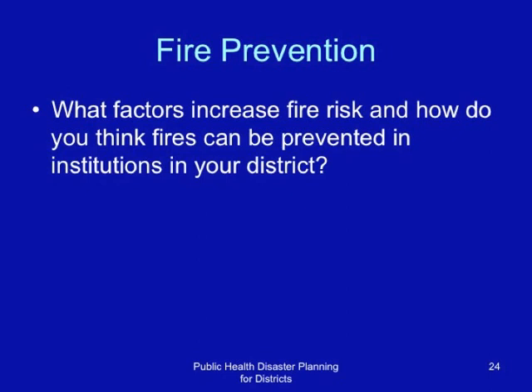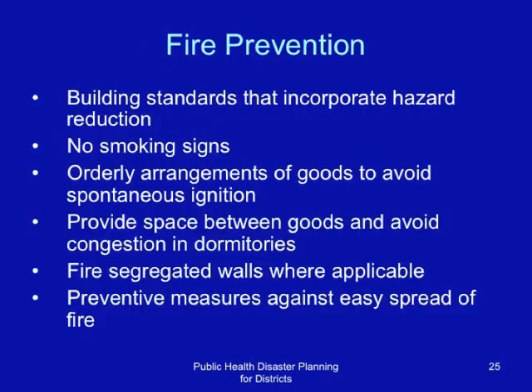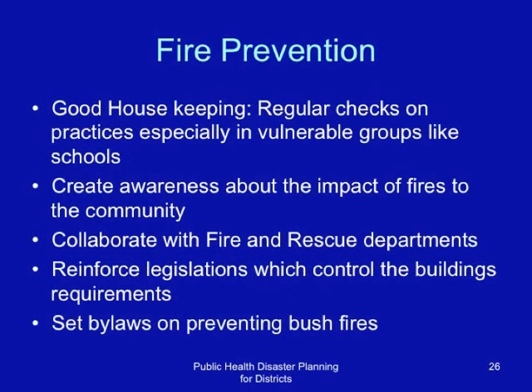Fire prevention includes building standards that incorporate hazard reduction, no smoking signs, orderly arrangement of goods to avoid spontaneous ignition, providing space between goods and avoiding congestion in dormitories, fire-segregated walls and preventive measures against easy spread of fire. It also involves good housekeeping, awareness creation to foster community responsibility, strengthening fire rescue departments, and enforcing legislation and by-laws to prevent fires.